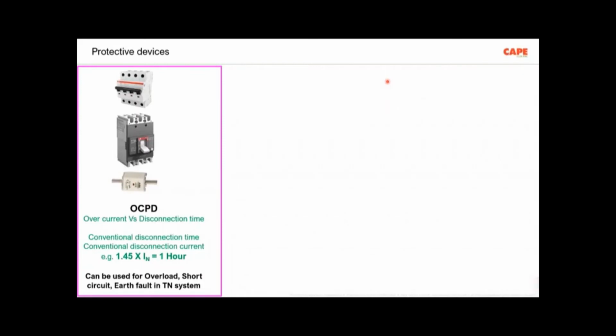I'm not going into it, but you should always keep in mind that there is a parameter called conventional disconnection time and conventional disconnection current. What it means is, the conventional disconnection current is 1.45 times the rated current of that particular protective device. Say, for example, you have a 10 amps MCB. This 10 amps MCB can take up to 1 hour to trip if the current is lesser than 1.45 times. What it means is, you have a 10 amps MCB, your overcurrent is 14 amps. How much time will it take the MCB to trip? Up to 1 hour. So your electrical wiring must be able to withstand that conventional time. So in electrical design, we are supposed to take care of this particular subject.